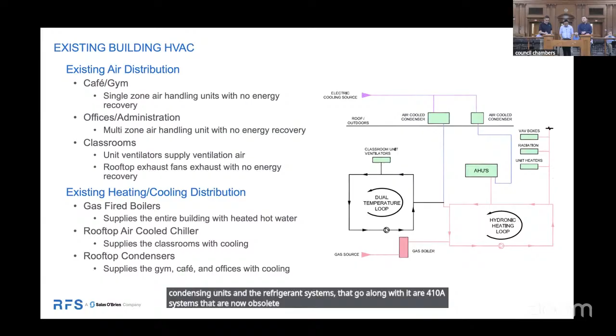Gas-fired boilers. The majority of classrooms are served with unit ventilators, not air handling units—air conditioning and ventilation is done through the unit ventilators. Most of this equipment is approaching end of life, ranging from 15 to 25 years life expectancy, and should be replaced. One part I neglected to mention is that the air handling units have a refrigerant-based cooling system. It's outdated—the air-cooled condensing units and refrigerant systems are 410A systems that are now obsolete and in pretty rough shape.